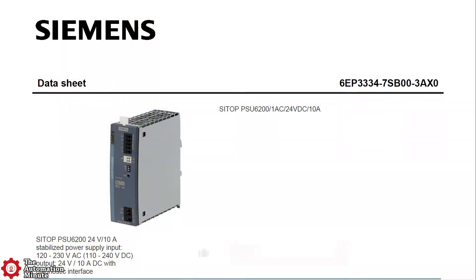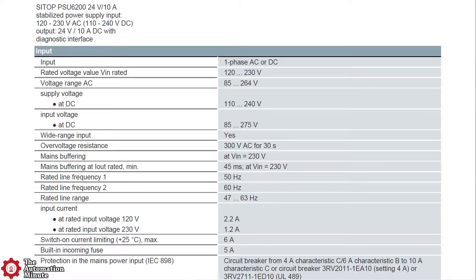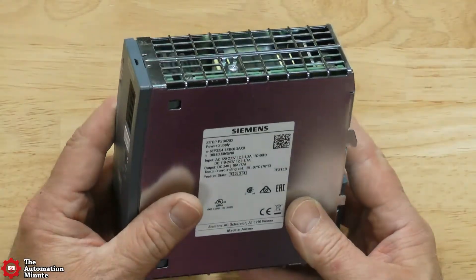Today we're taking a first look at the Siemens SITOP PSU6200, model number 6EP3334-7SB003AX0. It's a 24-volt, 10-amp stabilized power supply with an input voltage range of 85 to 264 volts AC, a frequency range of 47 to 63 hertz, and an input current rated at 2.2 amps at 120 volts AC.